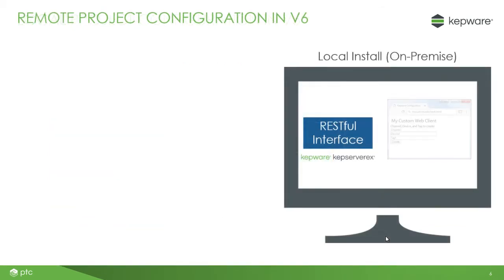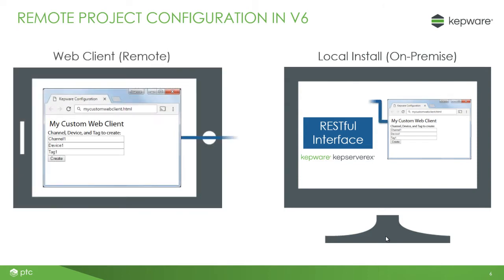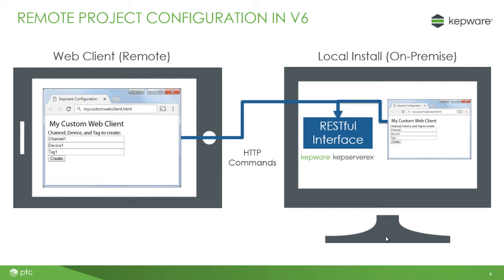Now, a RESTful interface allows third-party applications such as web clients, SCADA software that supports HTTP and IoT platforms, to make project changes to the configuration of KepServer EX both locally and remotely using HTTP commands. These changes include creating, reading, updating, and deleting objects such as channels, devices, and tags in the server.